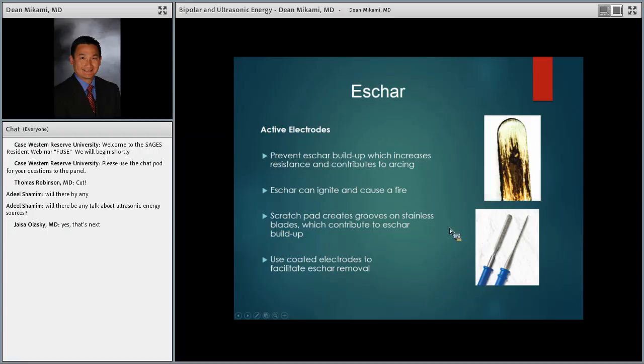We still use these, but scratch pads actually create grooves in the stainless steel of the blades, which can contribute to eschar formation also. Probably the best practice is to use a coated electrode. So when you want to remove the eschar that builds up after you use the instrument, you can get a gauze, or wet gauze, and wipe it off.